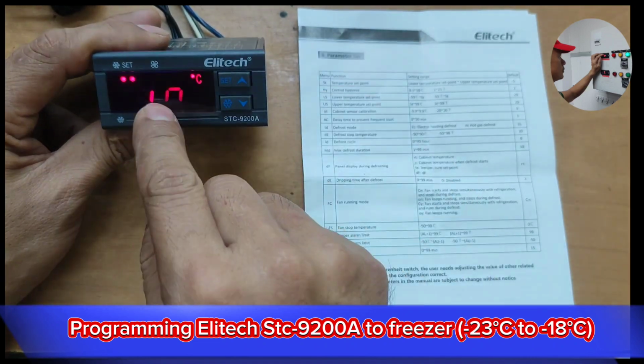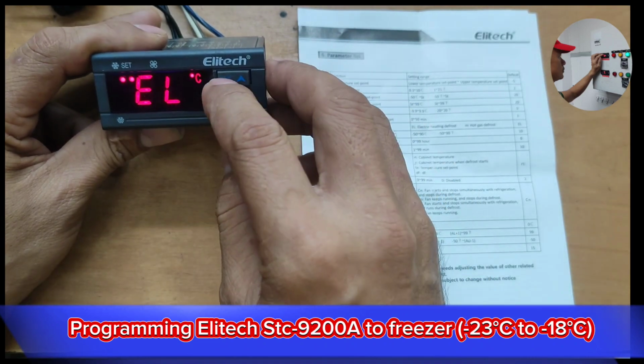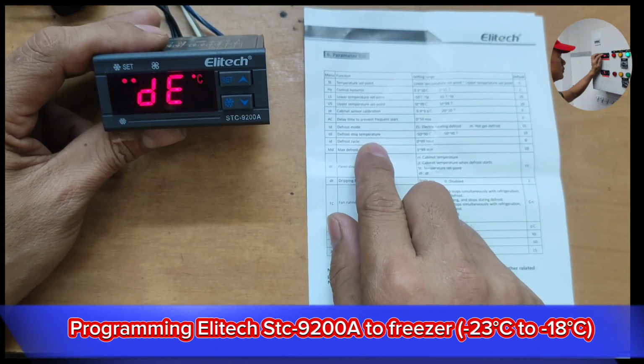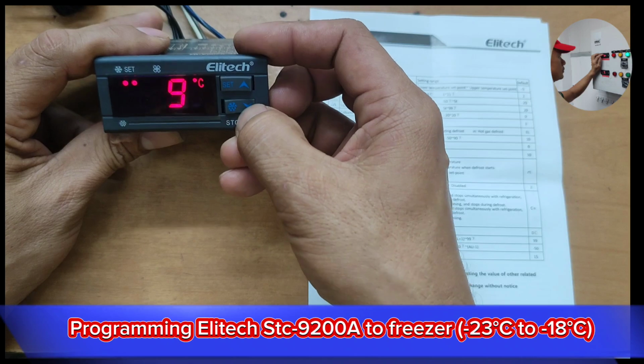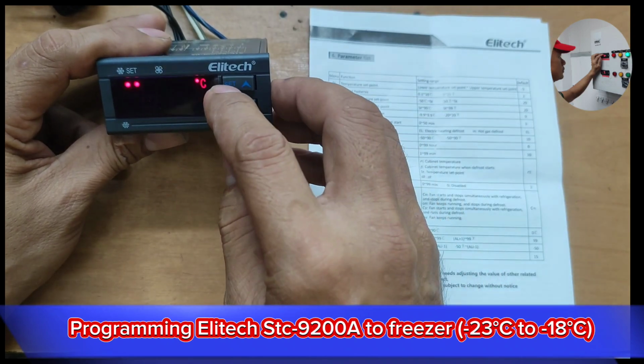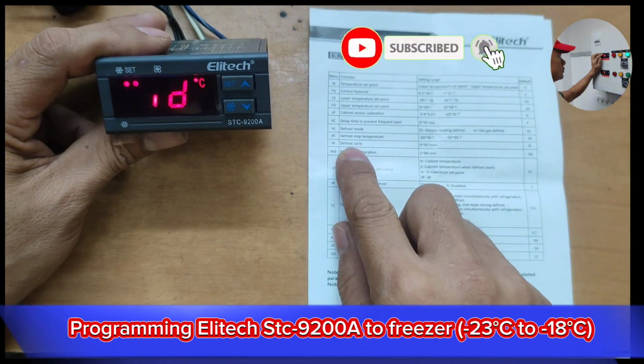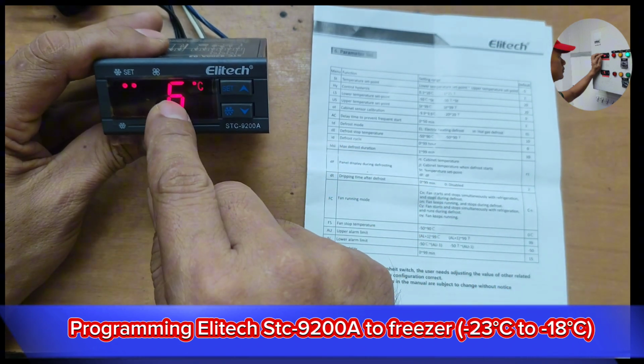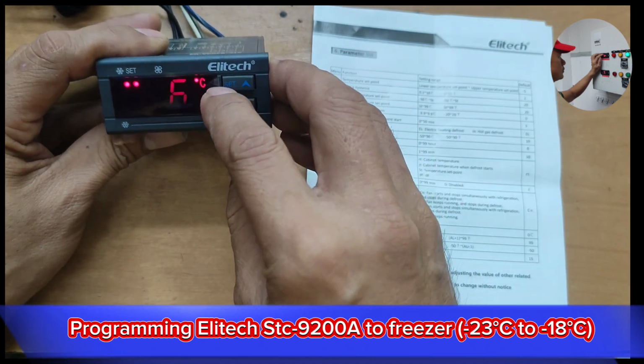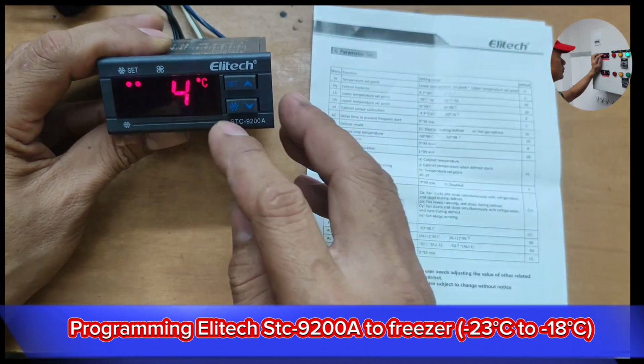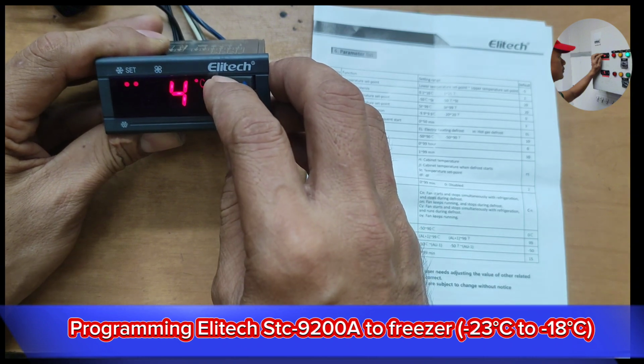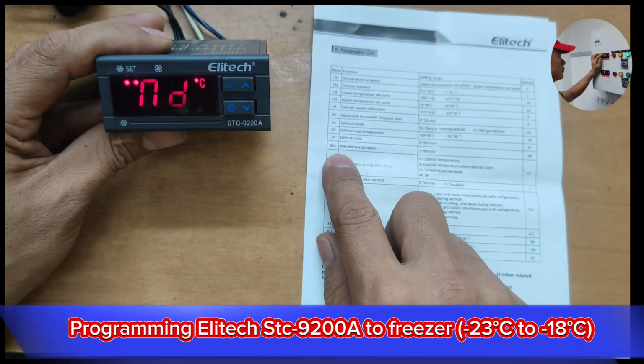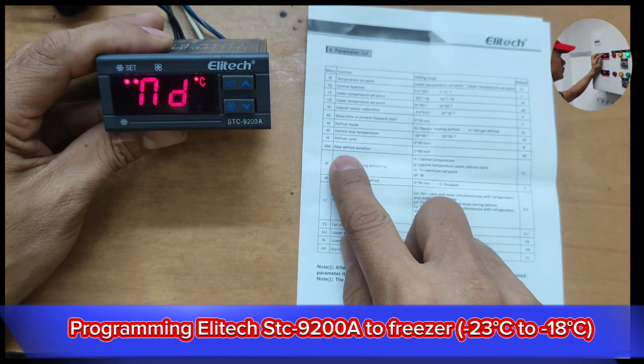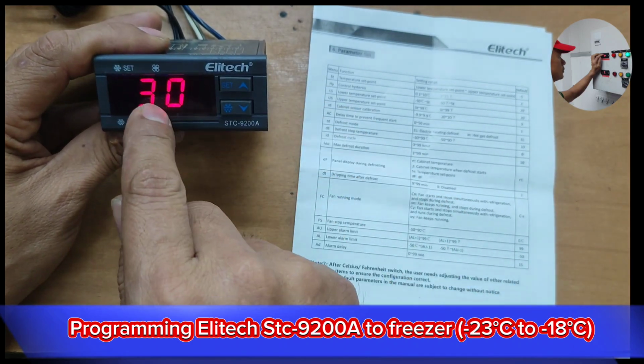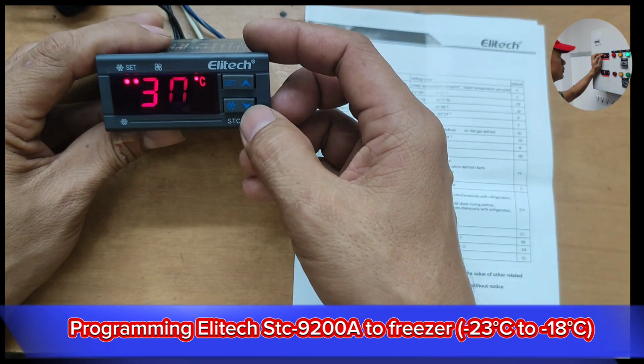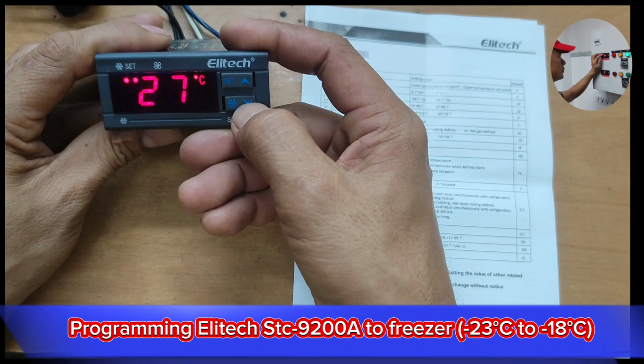I'm gonna show you that there is another option there. This is hot gas defrosting. So we choose electrical, that is the default. Preset, DE, defrost stop temperature. Preset, let's lower that to 8 degrees Celsius. That is ideal. And ID, defrost cycle. Preset, 6 hours is ideal for chiller. If you go to freezer, set that to 4 or 5. Every 4 hours, the freezer will defrost. Preset to memorize. Then the ND here is the max duration. Max defrost duration preset, and the default is 30 minutes. We're going to change that to 20.